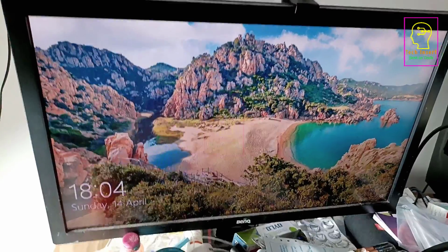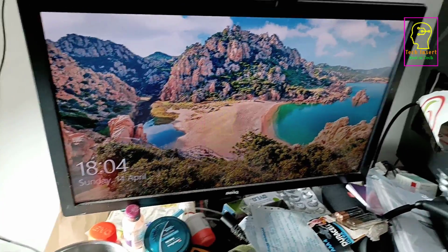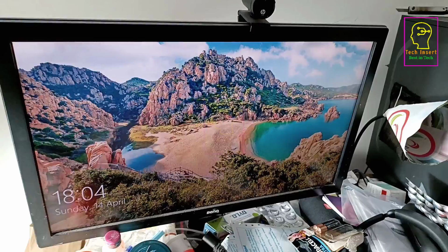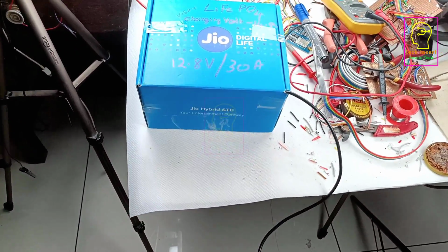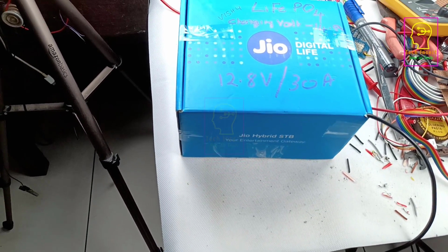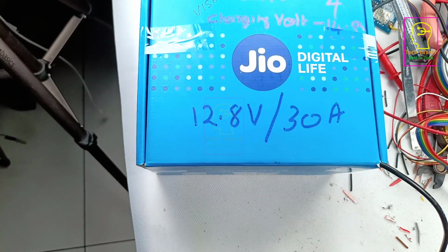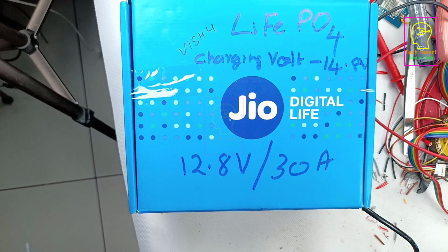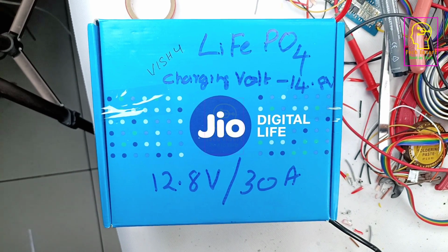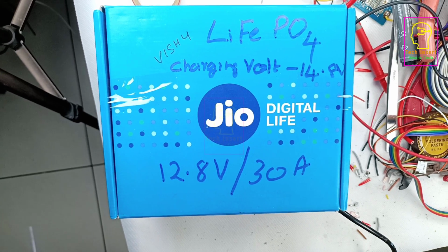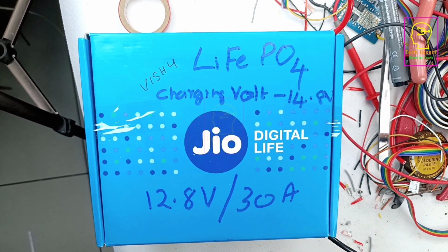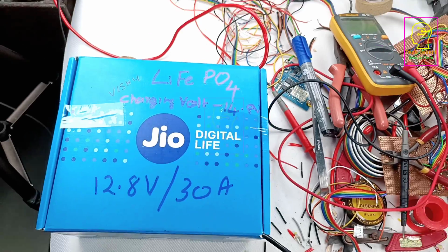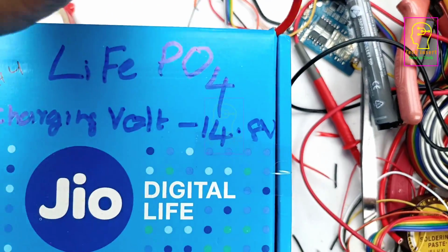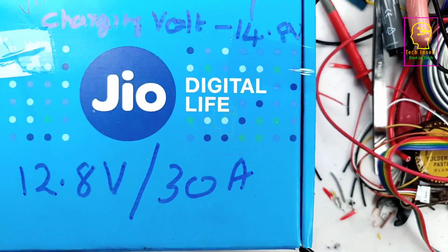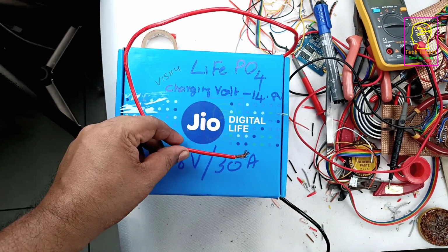I am switching off the recording, and I will come back just before the UPS becomes down due to low battery. We got more than 4 hours of backup time, more than 4 hours but not beyond 4 hours and 10 minutes. Up to 4 hours I saw it working, then I went outside and came back within 10 minutes, and when I came back the UPS was down. That means the backup time was maximum greater than 4 hours and less than 4 hours 10 minutes.